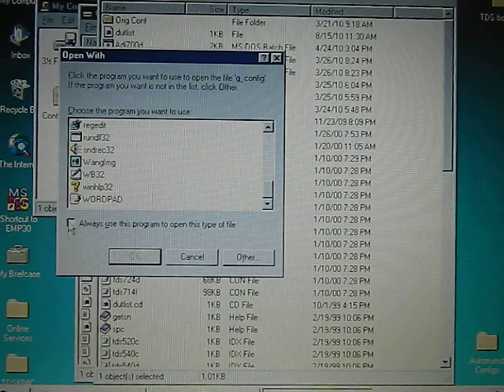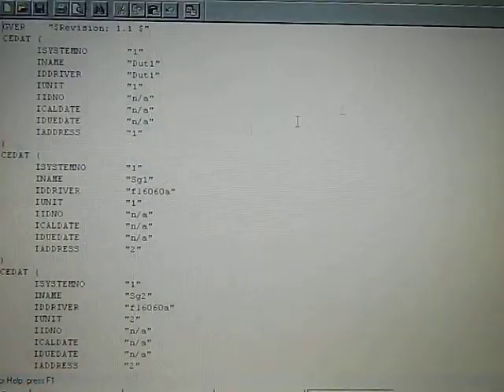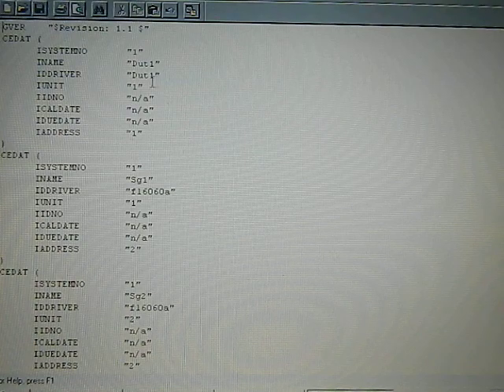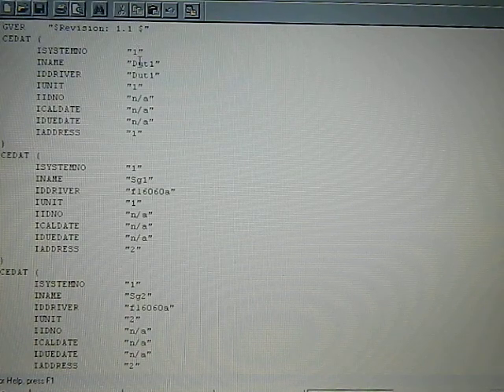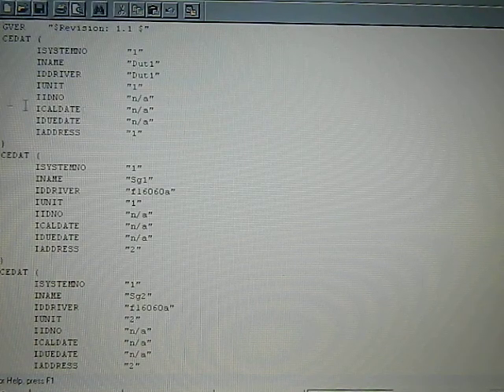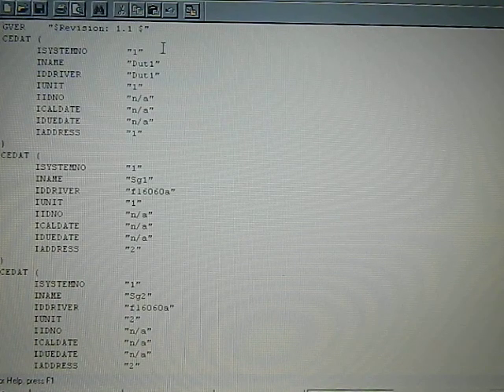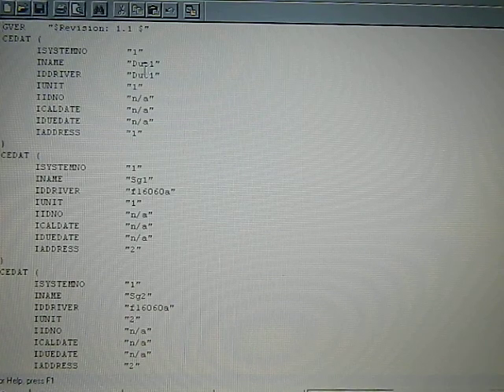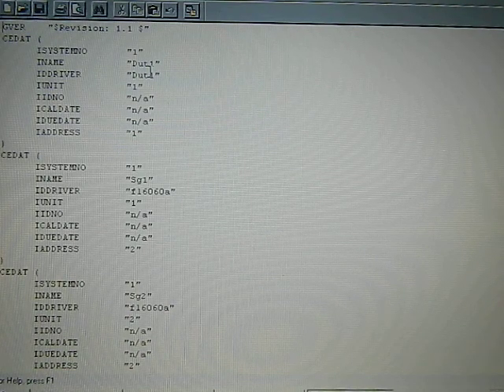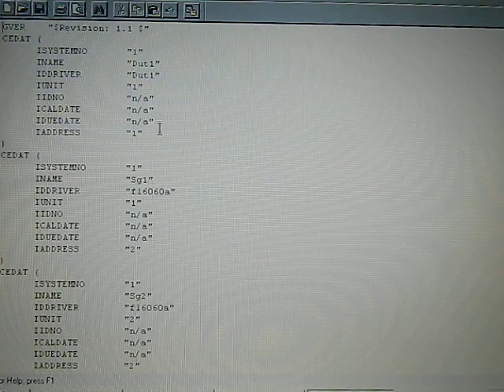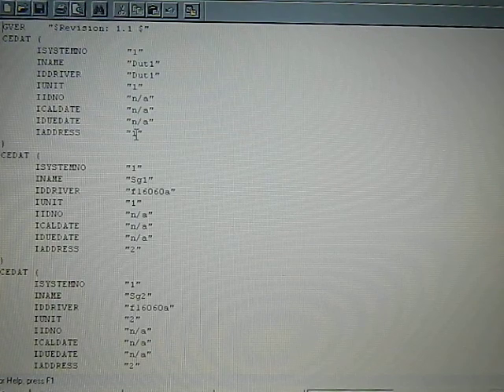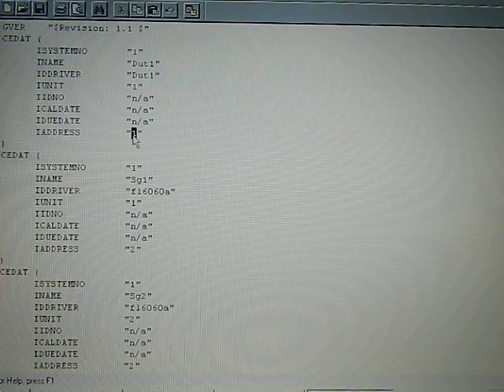And this is a working file. This actually works. So, system, this is all going to be system 1. The name, device under test 1, which is your scope, so you don't change that. And so you're going to set its address, its GPIB address, to 1.